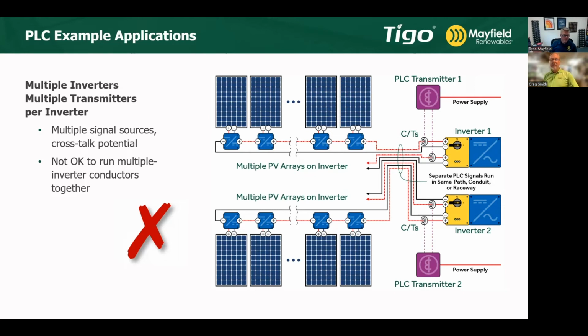The picture I'm going to show you was from a relatively new solar installer, one of the cleanest installs I'd seen in a long time. Their pipe runs were great, their work was great, and they had some cable tray in there too. They just didn't know. It wasn't laziness, because they probably spent more time doing some of what they did, but they were doing what they thought was efficient, minimizing pipe runs, running 1.25 inches instead of a couple of 3/4 inch runs. They were doing what made sense to them, and it unfortunately came back to bite them because they didn't understand this issue.